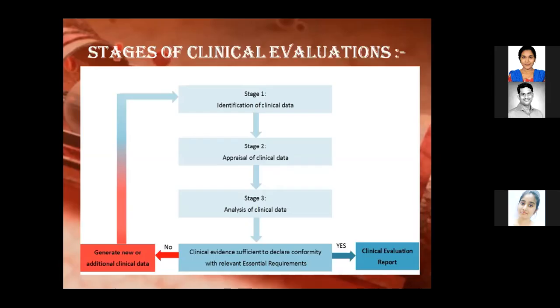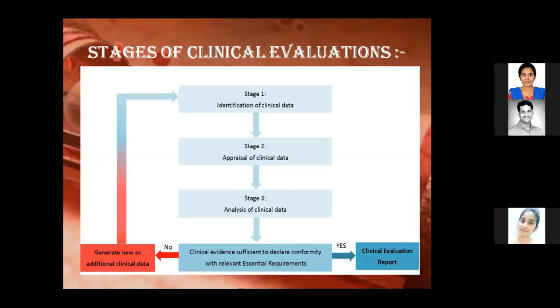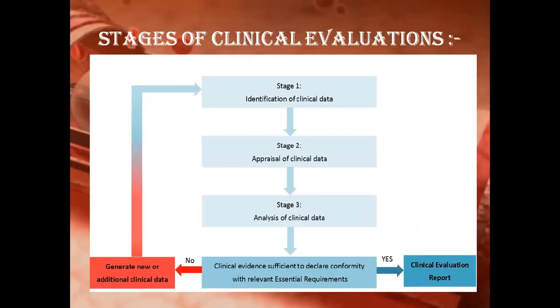And coming to stage 3, analysis of clinical data. In this stage 3, gap analysis is done and specific considerations are made. After that, if the clinical evidence is sufficient to declare conformity with relevant essential requirements, then the clinical evaluation report is done. If not, the evaluator should generate new and additional clinical data and go again to stage 1 and start from stage 1.